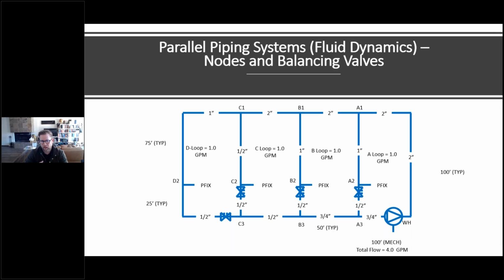And what we make the argument on in the ASPE General Design Guide is that yes, you should, because you need to know what the temperature is coming back to your water heater. Further, with the advent of a lot of heat pump water heaters, the return temperature is an important part in how that system operates. You may actually want to see a larger temperature differential through your system. So yes, you will need to know your hot water return temperature and try to do your best to capture what that is based off the calculations.